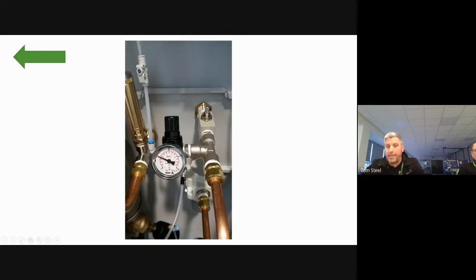Now, what you'll find is if the flow is turned up, so essentially, just for argument's sake, we've got 100 litres output of oxygen, and we're sitting at 94% oxygen content. If we increase the flow out beyond the design of the generator, so if we take, for example, 150 litres or 200 litres, the generator might supply that, but your purity will go down, okay? Your purity will go worse because you've exceeded the flow design of the generator, okay? And that's an important part to just remember.